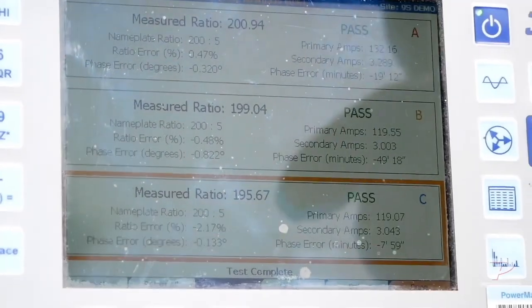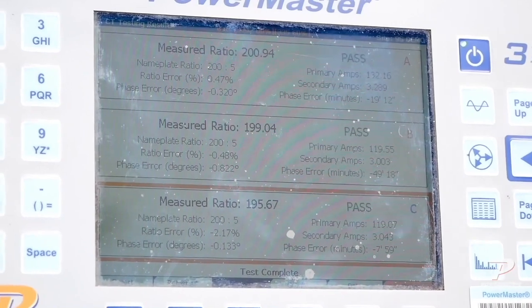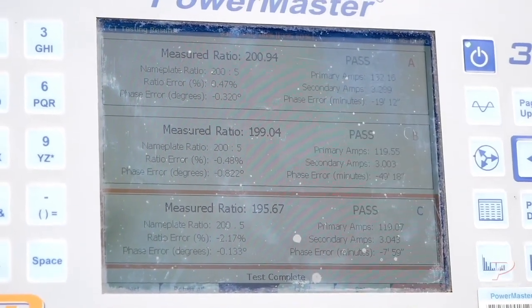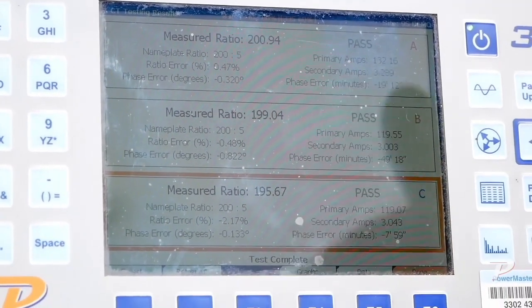So we got three passes right here, this is what we like to see. We would consider this site good, say the meter tested fine, and the CTs tested fine on this. So this would be a site where we've got a good test.